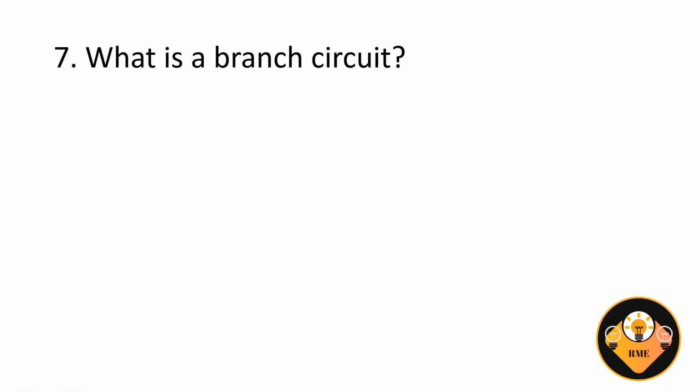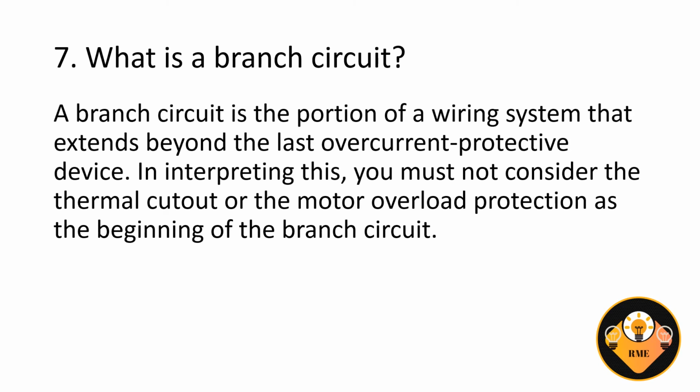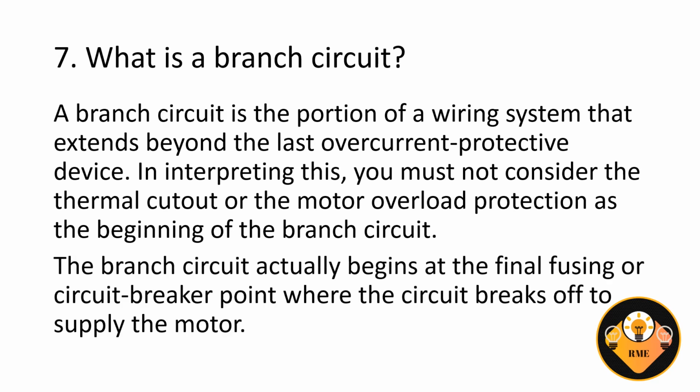Number 7. What is a branch circuit? A branch circuit is the portion of a wiring system that extends beyond the last overcurrent protective device. In interpreting this, you must not consider the thermal cutout or the motor overload protection as a beginning of the branch circuit. The branch circuit actually begins at the final fusing or circuit breaker point where the circuit breaks off to supply the motor.